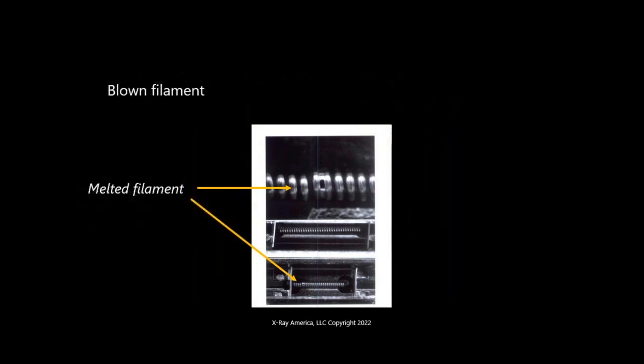The other thing that can happen is filaments can die two ways. If you put too much voltage on a filament, and it often happens to the small one, because they're trying to get high resolution, a lot of power to the small, it can be melted. So you get a tube back under warranty and you see this is a melted filament. This was too much power. The other problem is intergranulation in filaments, where the filament just kind of cracks. It has to do with some material failure in the tiny tungsten filaments. So it cracks, and that's a manufacturing defect too.